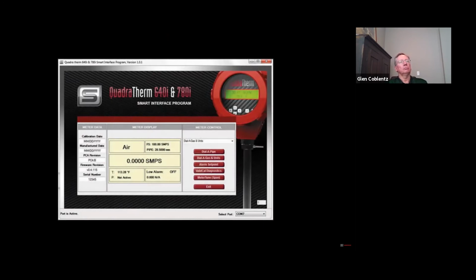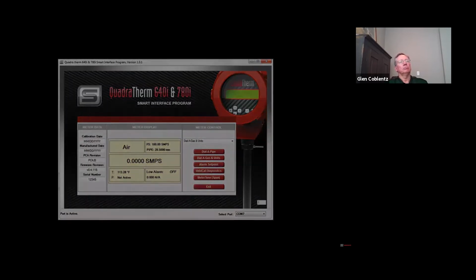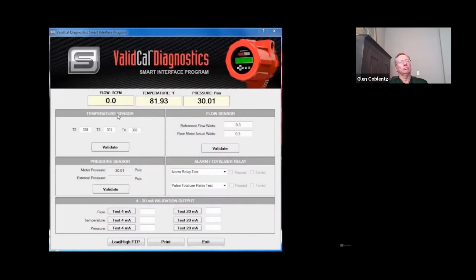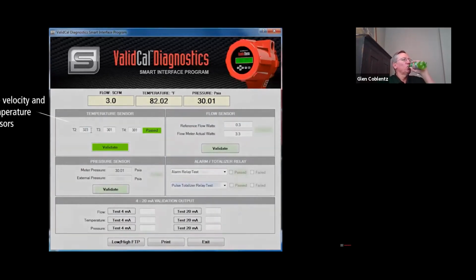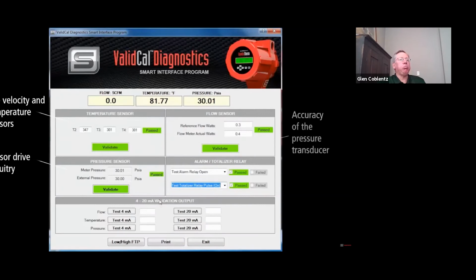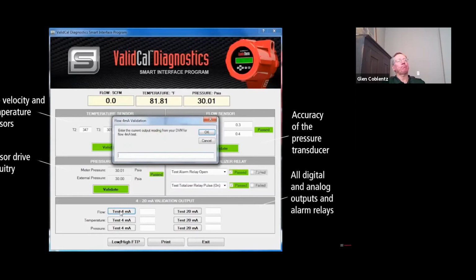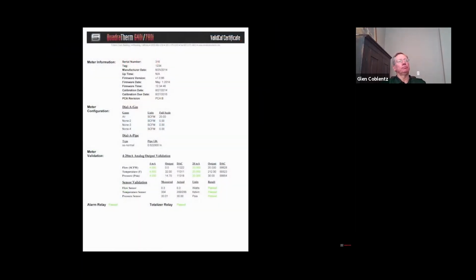Sierra offers a free in situ calibration validation software package we call ValidCal Diagnostics. Unlike some other validation routines, Sierra's ValidCal Diagnostics program provides a complete check of all the meter's components, including the velocity and temperature sensors, sensor drive circuitry, accuracy of the pressure transducer, and all digital and analog outputs and alarm relays. When complete, a detailed calibration certificate and diagnostics report is created. All of this can be accomplished without even removing the meter from the process piping.